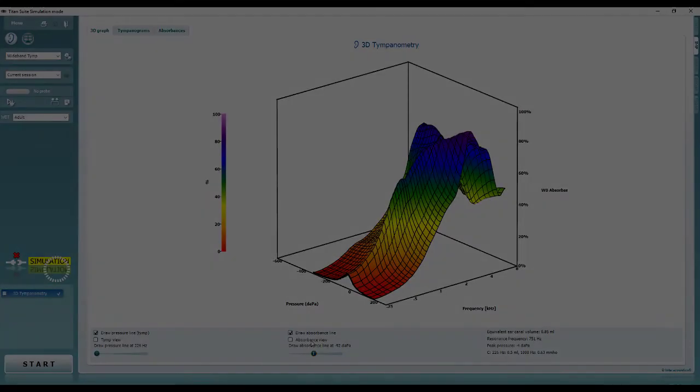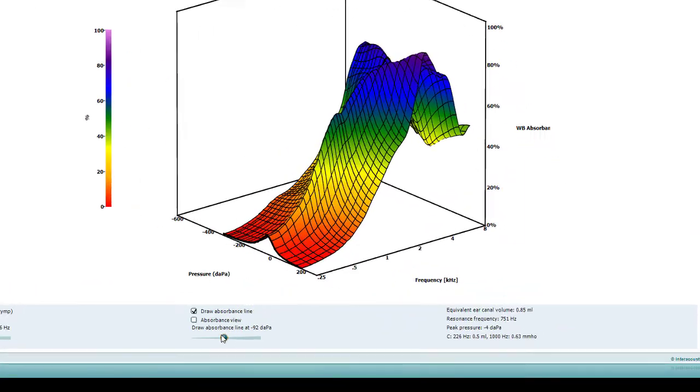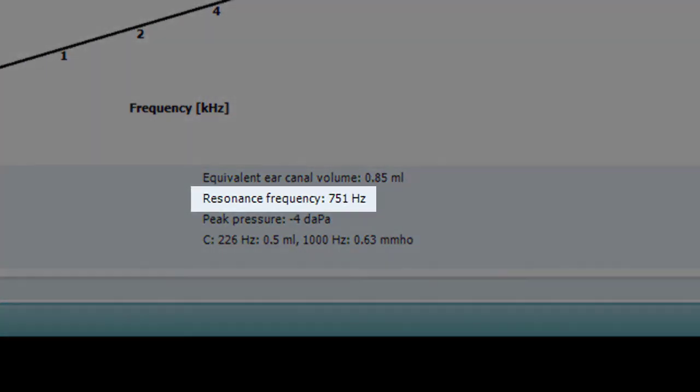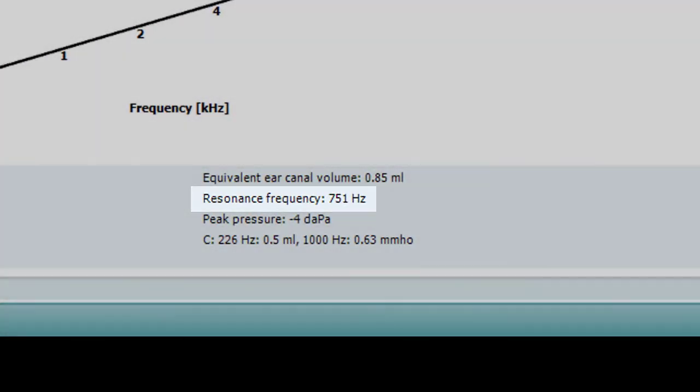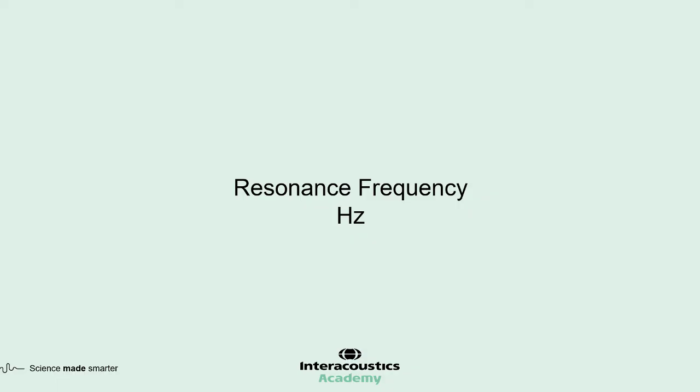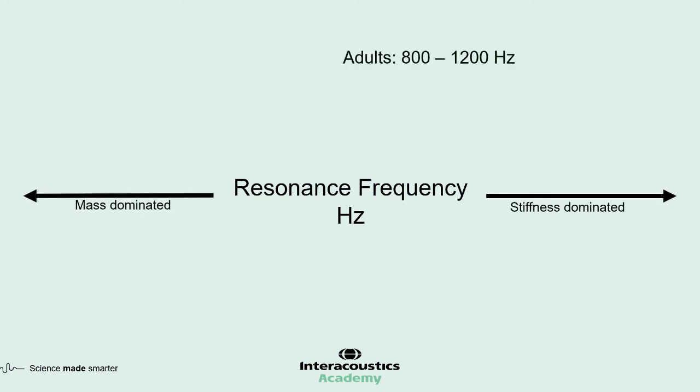During a wideband tympanometry measurement, a value called the resonance frequency is also recorded. This is the probe frequency which is sensitive to a change in both mass and stiffness, and so will change according to pathologies. The resonance frequency for an adult is around 800 to 1200 Hz, and 250 to 600 Hz for an infant.